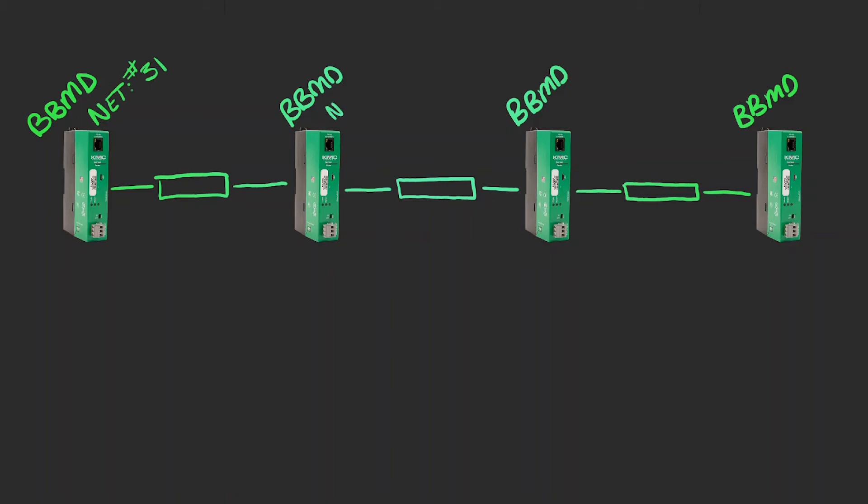But since it is a BACnet network, it is required to have its own unique BACnet network number. All BBMDs on this same network need to be configured with this same unique network number, or they'll get confused trying to route messages.